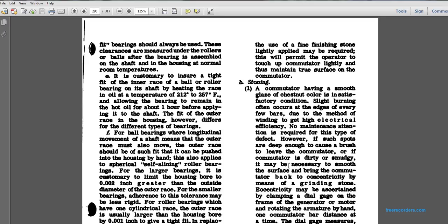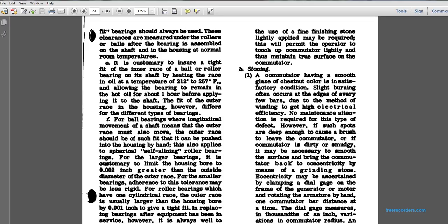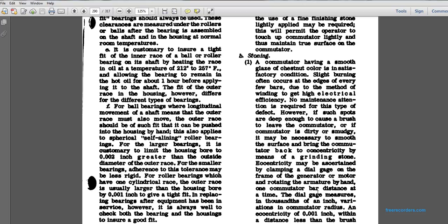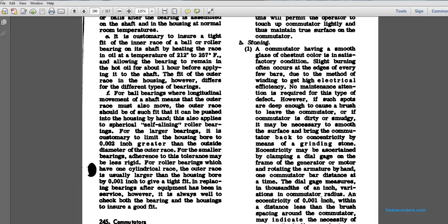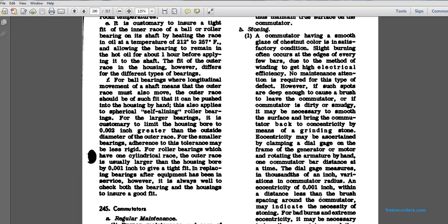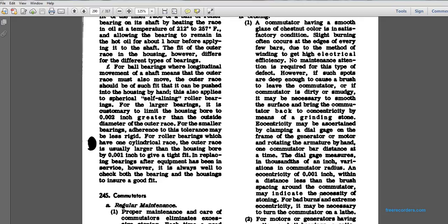However, if such spots are deep enough to cause a brush to leave the commutator, or the commutator is rough, dirty, or smudgy, it may be necessary to smooth the surfaces and bring the commutator back to concentricity by means of a grinding stone. Eccentricity may be checked by clamping a dial gauge on the frame of the generator or motor, rotating the armature by hand one commutator bar distance at a time. The dial gauge measures the thousandths of an inch variation of the commutator radius. Any eccentricity of 1/1000th of an inch within a distance less than the brush's space around the commutator may indicate the necessity of stoning.